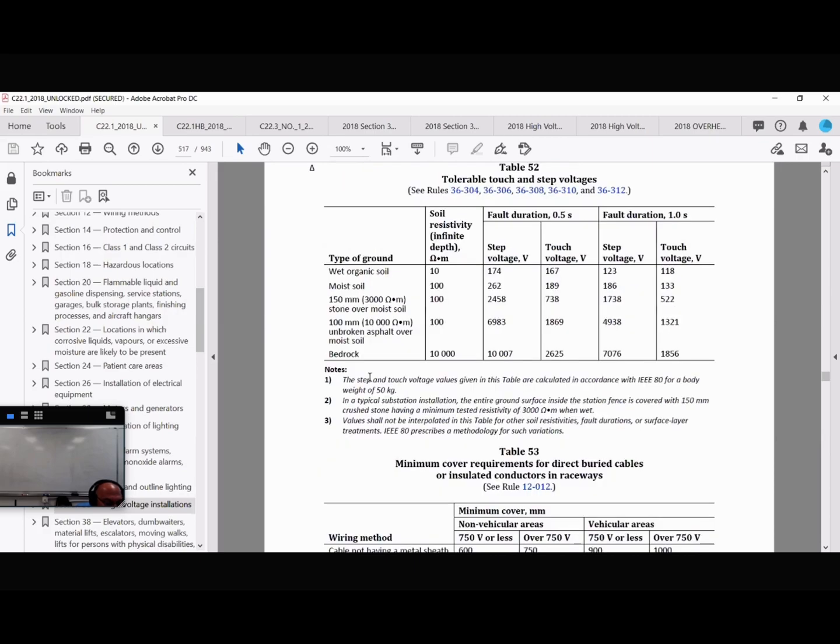Now, where do you manage to get the available fault currents? Who gives them to you? Engineer. Supply authority. Where does the engineer get them from? Supply authority. An engineer at the supply authority. There you go. So you're right in both cases. So you have to get the available fault current from the utility, and then you have to do resistance tests.